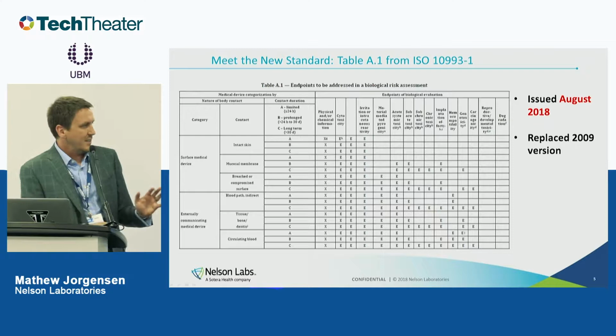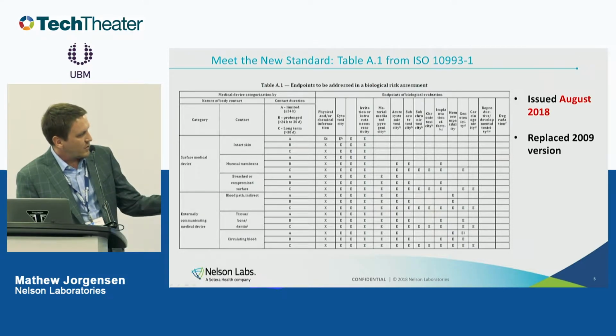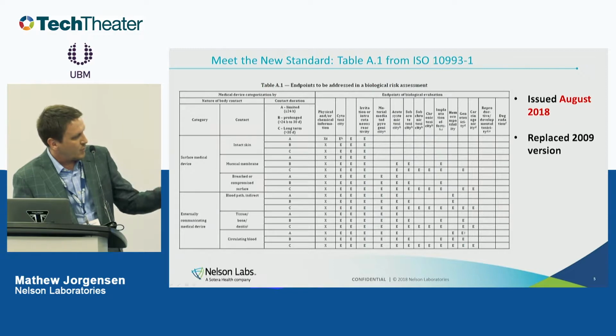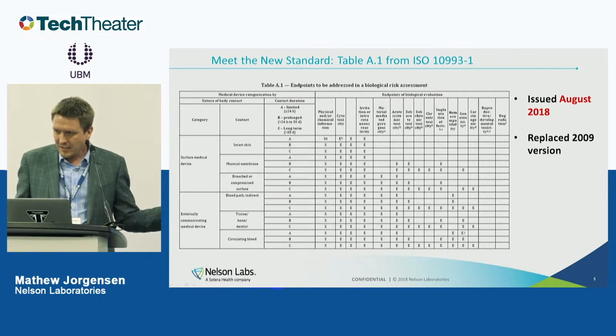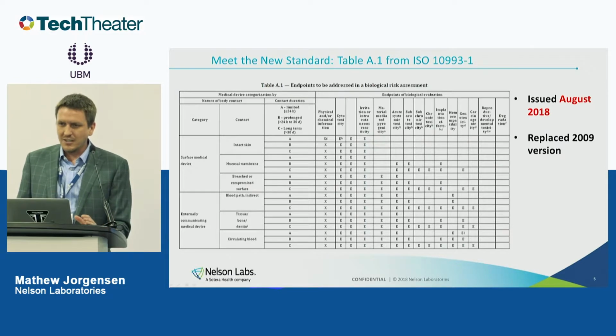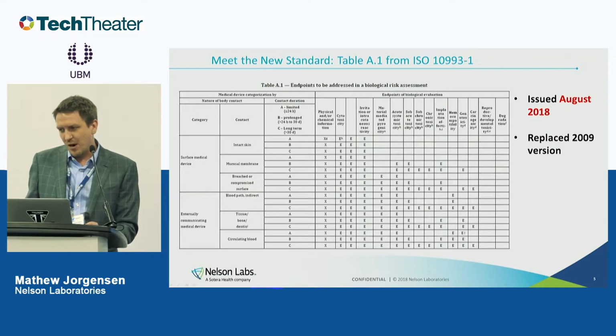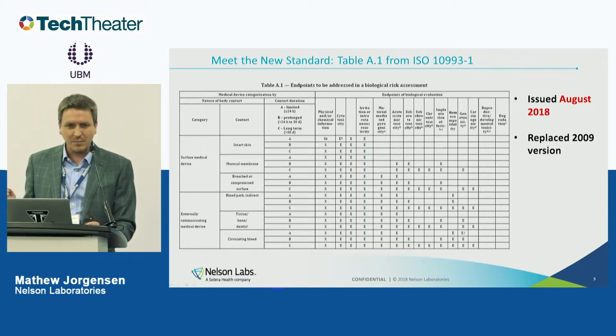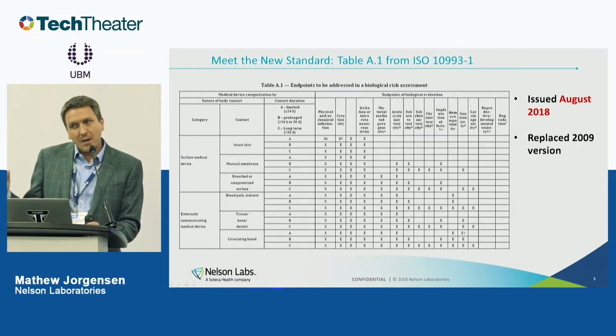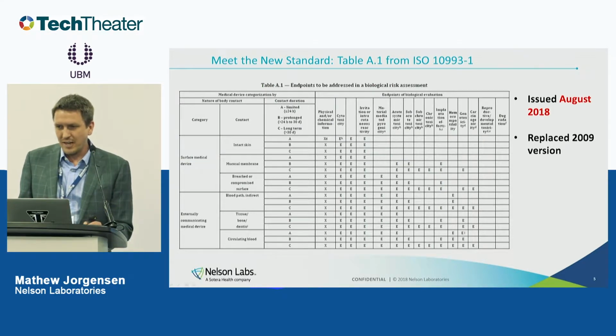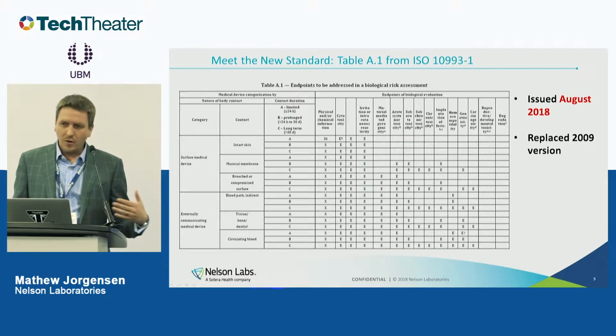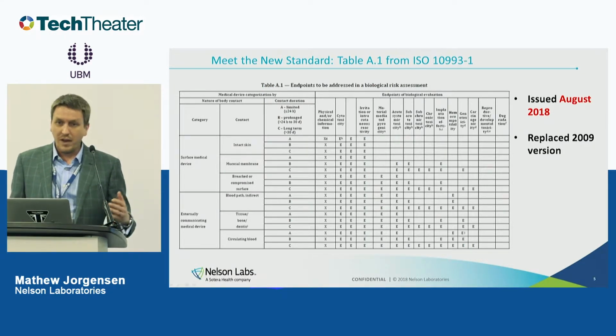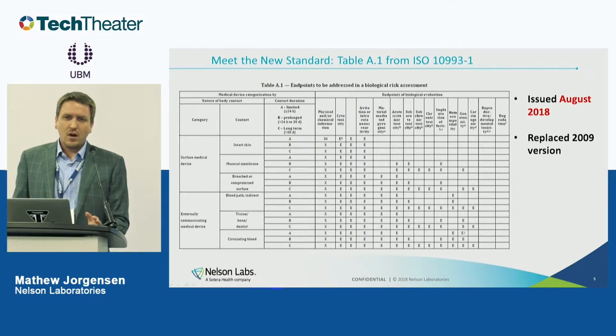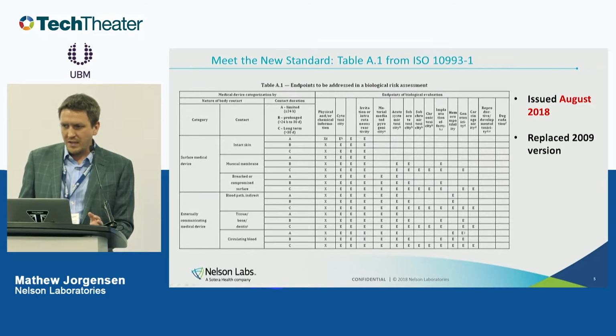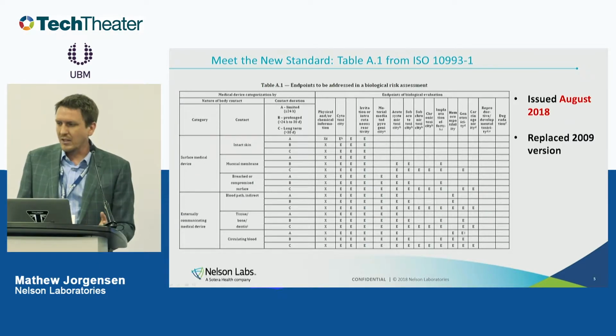So this really sticks out, because in the previous version of this table, in the last version of 10993-1, these were all X's here instead of E's. But they replaced the X's with E's to remind you with every single little box in that matrix that, okay, we're not just Xing something off, we're evaluating, right? And evaluating means that you might be able to evaluate not with just a test, right? It could be that you can evaluate by understanding your materials really well, or by borrowing some other data. And there's lots of ways to evaluate the safety of your device and these biological endpoints other than a test.